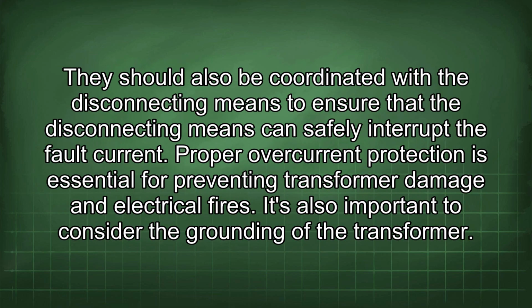They should also be coordinated with the disconnecting means to ensure that the disconnecting means can safely interrupt the fault current. Proper overcurrent protection is essential for preventing transformer damage and electrical fires.